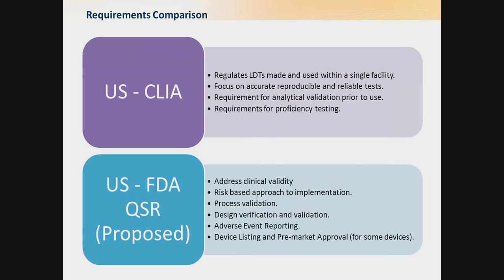The requirements can be seen to be contrasting but also essentially overlapping. CLIA regulations regulate LDTs made and used within a single facility, focusing on accurate, reproducible and reliable tests, with requirements for analytical validation prior to use and proficiency testing. The proposed FDA quality system requirements address clinical validity, taking a risk-based approach to implementation, process validation, design verification and validation, adverse event reporting and device listing.